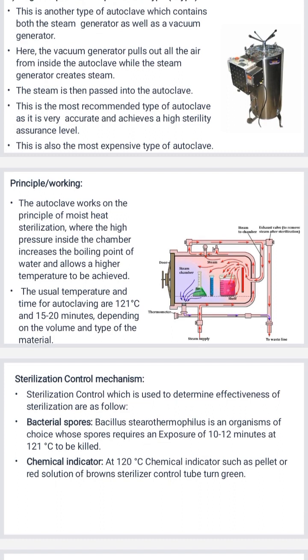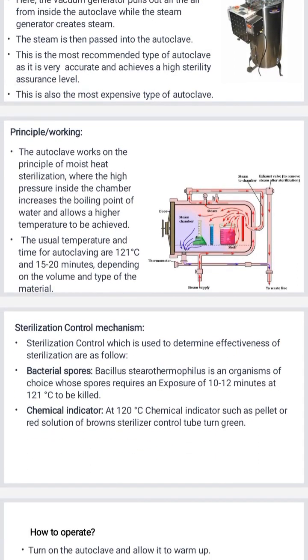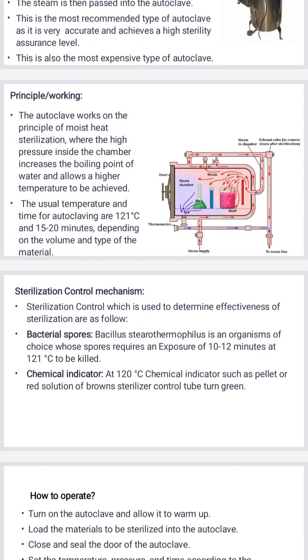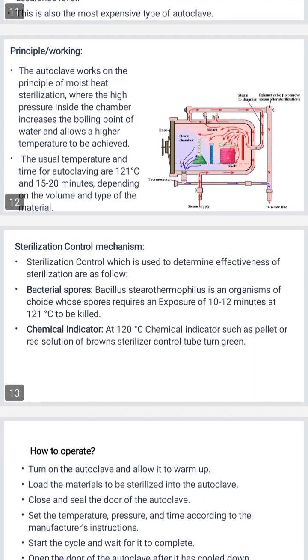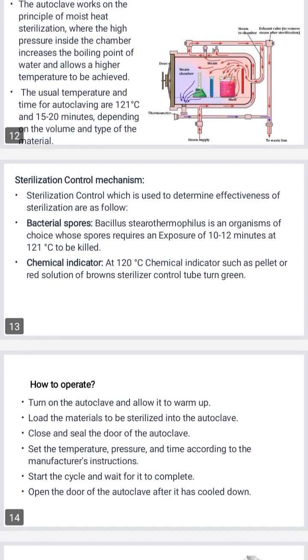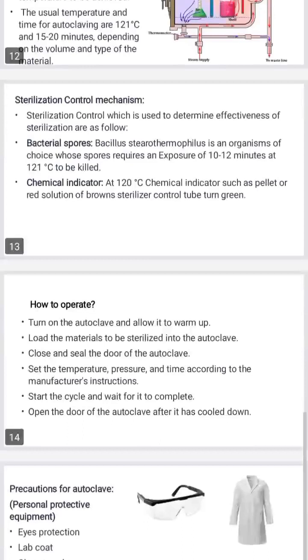Sterilization control mechanism. Sterilization controls which are used to determine the effectiveness of sterilization are as follows. Bacterial spores: Bacillus stearothermophilus is the organism of choice, whose spores require an exposure of 10 to 12 minutes at 121 centigrade to be killed. Chemical indicator: at 120 centigrade, a chemical indicator such as a pellet or red solution of brown sterilization control tube turns green.